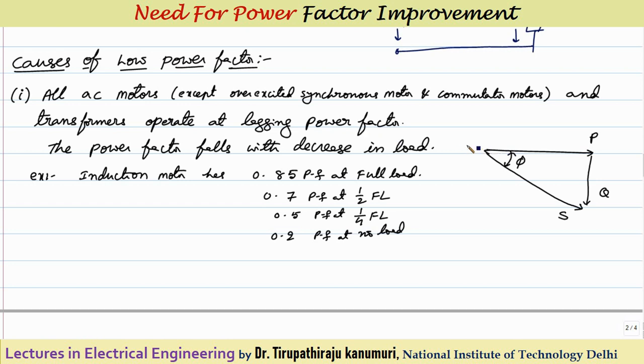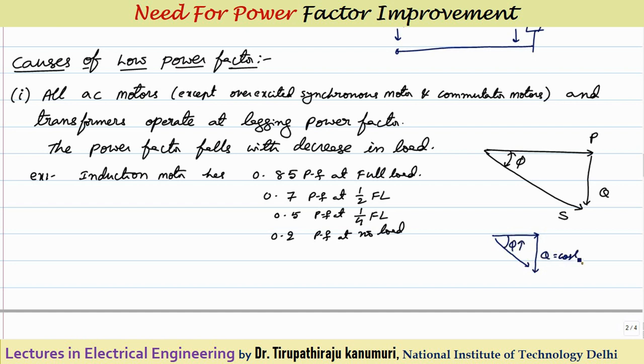For any AC machine or transformer, the reactive power from no load to full load varies very little — Q is nearly constant. But since load is expressed in terms of active power P, as the load decreases, P decreases while Q stays roughly constant. Because the power factor angle phi depends on the relative magnitudes of P and Q, if P decreases with Q constant, the angle phi increases and therefore the power factor decreases.